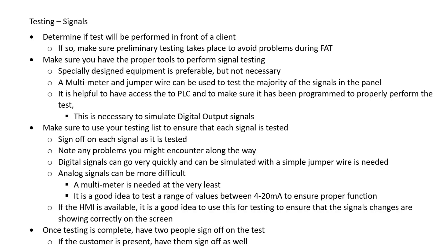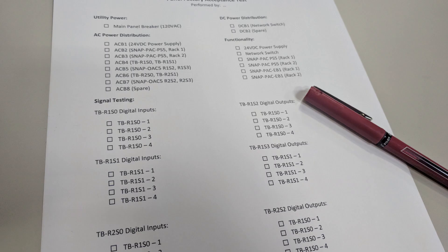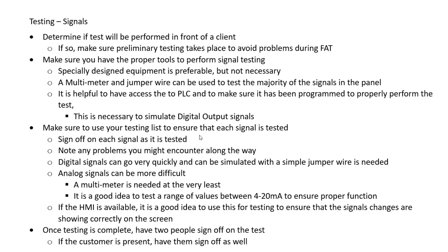From this point, we simply start testing our signals using the list we have created to make sure that we test every single signal. As we go through this, we sign off on each signal as it is tested. We want to make sure that as we encounter problems, we note those problems, keep a record of those issues, and address them once the test has been completed.